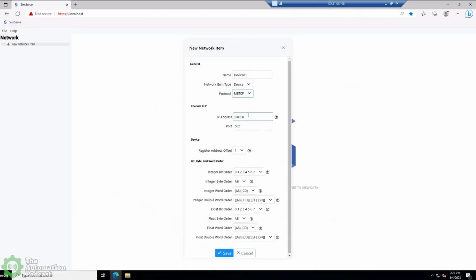Next up, we can assign an IP address to the device as well as the port that this device will be listening to Modbus requests on. When you take a look at the IP address, by default it has all zeros in there, and that basically means the device is going to respond to any IP address that is assigned to the host. I'm just going to leave it that way for this example. You can see the IP address of the host up here at the top of the RDP session, so that's what we'll be using on the Ignition side. And then port 502, that's the standard Modbus port.